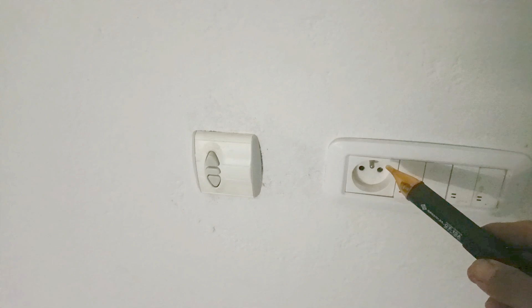The problem with those non-contact voltage detectors is that they can't detect the wire inside the wall. I will do a test now. Those detectors can't detect a wire inside the wall. For example, here I knew there is a wire going up, but it's not detected. They can detect only inside the socket, near the socket. Here they can't detect anything.